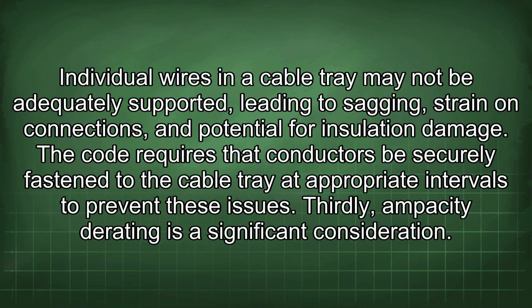Individual wires in a cable tray may not be adequately supported, leading to sagging, strain on connections, and potential for insulation damage. The code requires that conductors be securely fastened to the cable tray at appropriate intervals to prevent these issues. Thirdly, ampacity derating is a significant consideration.